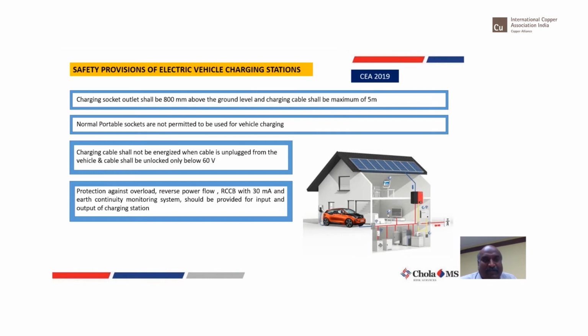The charging socket outlet shall be 800 mm above the ground level, which is given in CEA clearly, and the charging cable shall be a maximum of 5 meters. For example, if this is your charging box from where you are going to charge your two-wheeler or a car, the length of the cable should not be more than 5 meters. Don't think, okay, I have my parking bay in some corner, and from there to here I will lay an underground cable and connect over here. Please have a look at it. More than 5 meters is not allowed, and they shall be placed at 800 mm above the ground level.